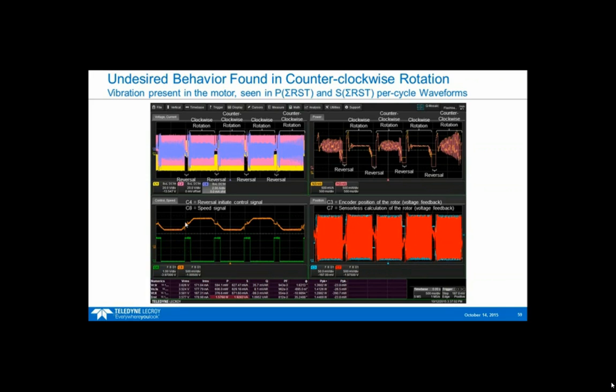The customer was also looking at some of their control signals. This C4 signal right here is when the reversal should occur, so he's trying to monitor that. C8 is the speed signal he's monitoring, and these are the encoder position signals. The C3 and C7 waveforms, one is the encoder position voltage feedback signal, and the other, this blue or red trace, is used to cross-check this calculation. So he was comparing those as well and making sure they tracked, getting a lot of feedback here. But the primary thing to look at is, why is this clockwise rotation operating so much better than the counterclockwise rotation?